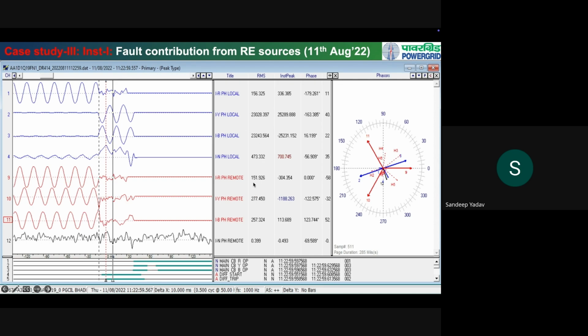And if you take a look at their phase angles, the R phase is at 0, the Y phase is minus 122, and B phase is plus 122 or minus 240 degrees. So this is the positive sequence current. Positive sequence is nothing but a balanced R, Y, and B system.